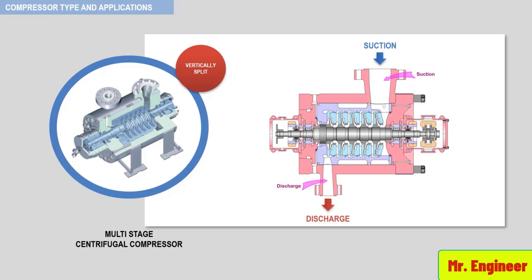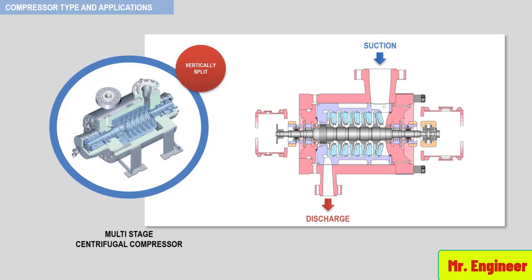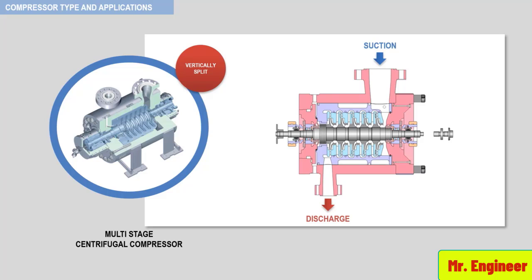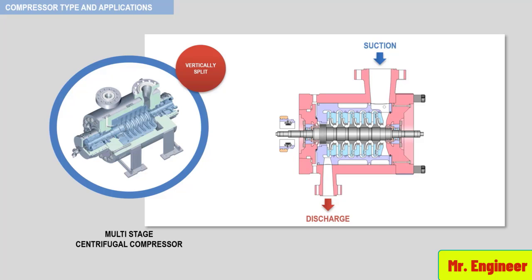Let's disassemble the various components to understand the respective arrangement in this typical barrel centrifugal compressor. We begin by removing the bearing housing cover. Then, the bearing housing is removed. Next, we split the thrust bearing assembly. Then, we remove the thrust collar assembly. Next, we remove the coupling. Then, we split the radial bearing on the non-driver end, then the radial bearing on the driver end. Then, we remove the sealing arrangement on the non-driver end, then the sealing arrangement on the driver end.